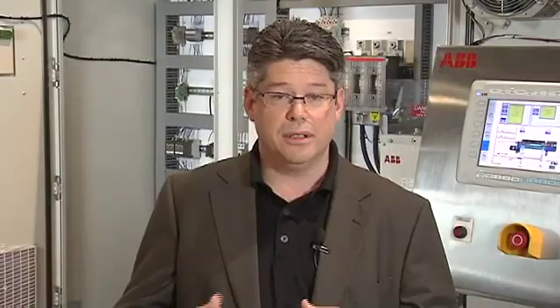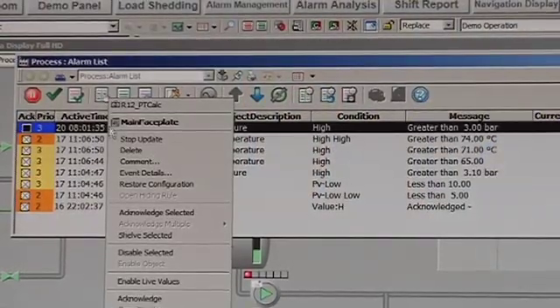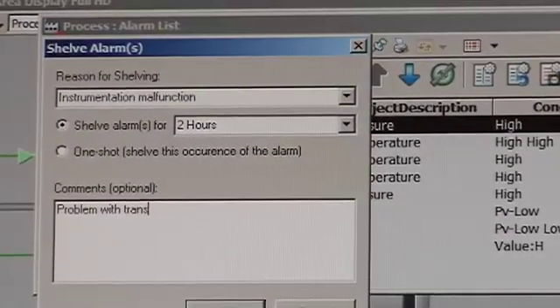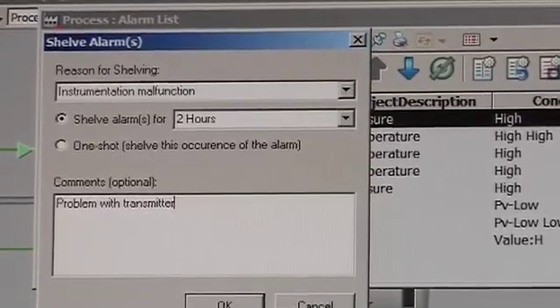When it comes to alarm management, in a PLC application there are multiple places where you have to manage alarms — it could be in the controller, it could be up in the HMI — and when applications get too large, this can get quite complex over time. DCS systems are architected to handle a large amount of alarms and present them to many operators. They also help create an alarm management strategy with features such as alarm shelving, alarm hiding or dynamic suppression, and alarm analysis.